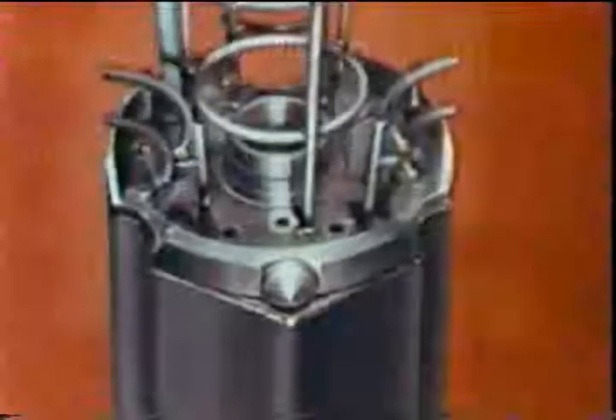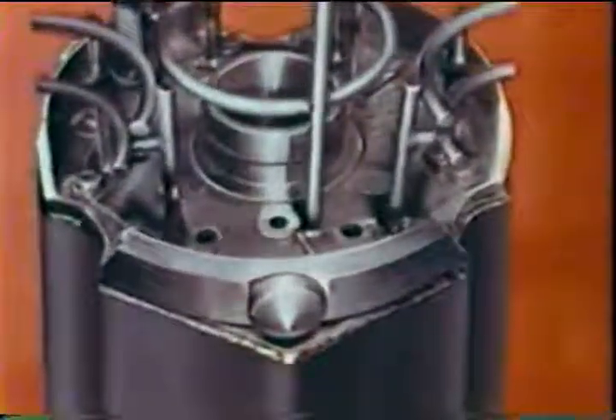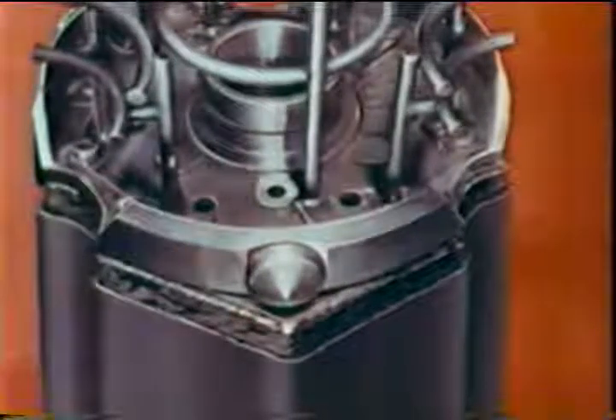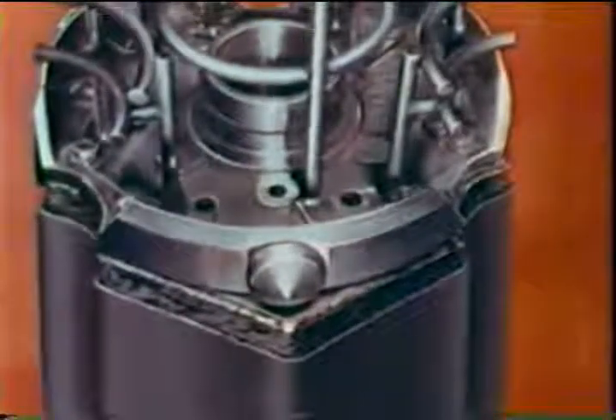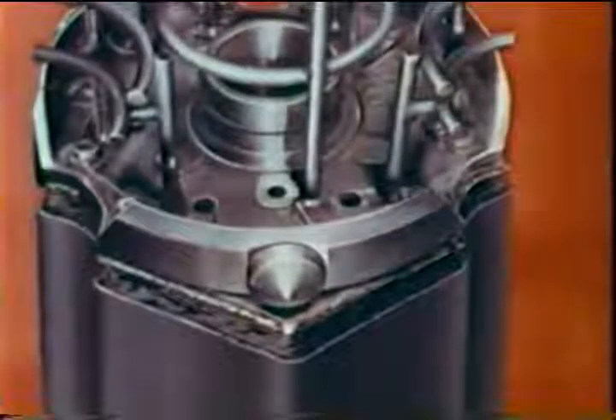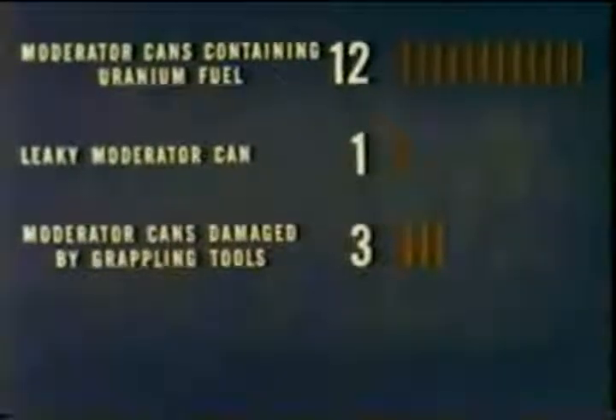On the basis of initial examinations of the damaged core, 13 moderator cans were scheduled to be removed from the reactor. 12 contained fuel, and the other, which was free of fuel, had a leak. In the latter case, the sodium-laden graphite, which had swelled approximately 1%, ruptured the head of the moderator can. Three more moderator cans were damaged while removing debris from the core top, and also required replacement. This brought the total number of moderator cans which had to be replaced to 16.